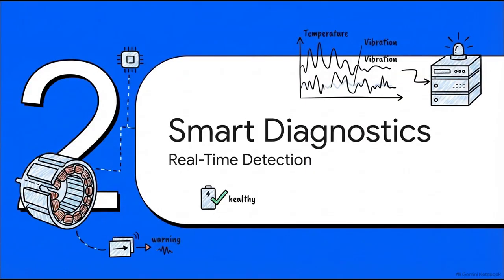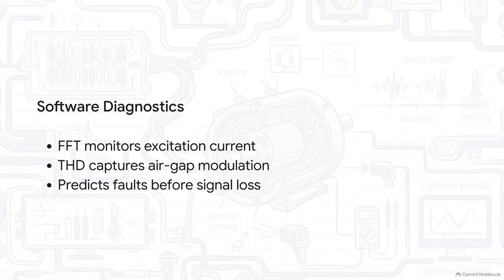Section 2. Real-time smart diagnostics. All right, so the physical hardware is failing and the signals are dropping. Now let's dive into the software immune response. It's programmed to catch these microscopic changes in real time, way before a total breakdown occurs. It's incredibly sophisticated. The system constantly runs a fast Fourier transform, or FFT, on the sensor's excitation current. It's actively on the hunt for total harmonic distortion.